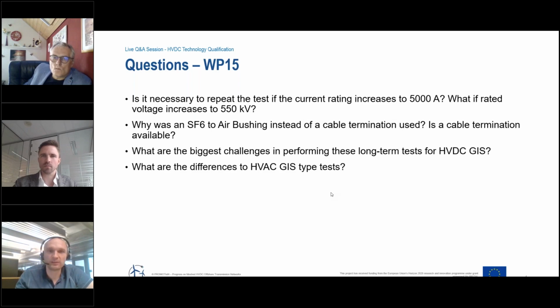So this is a major addition, and another is the insulation system test, where you combine the thermal and dielectric stress to really get the insulation to the critical point in DC, where you try to reach the DC steady state. That's an addition, and it's a quite long test, more effort, because you combine high current and high voltage testing. But if we look at the GIS as a complete product, there's also a lot that is identical, for example a gas tightness test, a mechanical endurance test for a disconnector, or a short-time withstand current for the components. They are basically the same, and in some cases we can even take results from an AC GIS with a similar design.